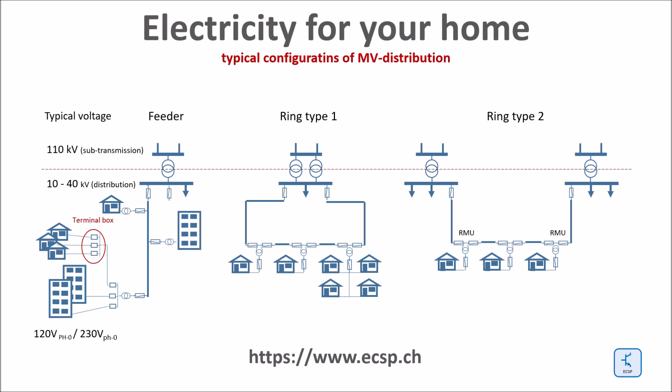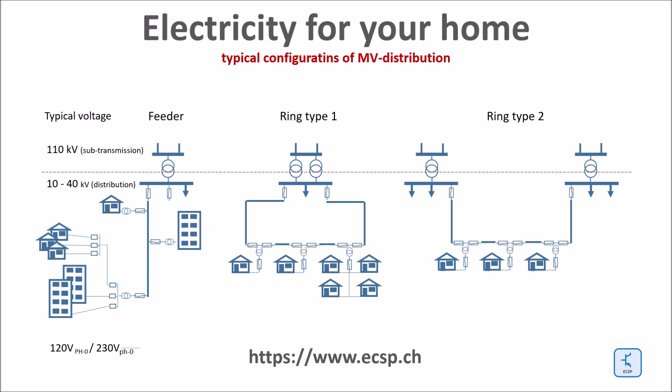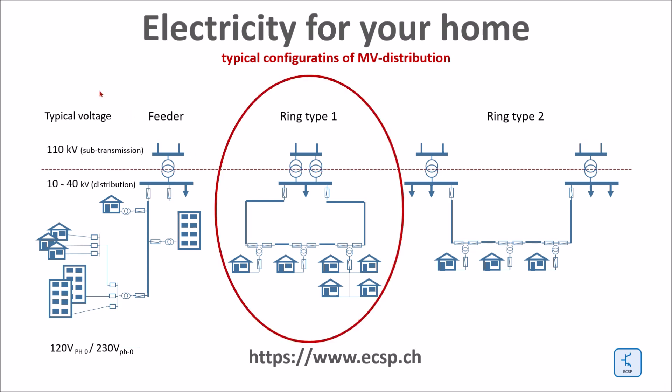So far we have seen the terminal box and the secondary substation connecting low-voltage to medium-voltage. Now we are looking at the primary substation, including the configuration of the medium-voltage distribution. The primary substation connects the medium-voltage to the high-voltage grid. The simplest configuration is a feeder arrangement. In rural areas this can even be single-phase. A failure along the line is cleared by the breaker in the primary substation, and the feeder stays out of service until repair.